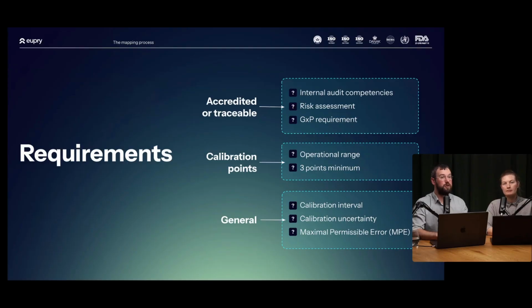You need to have a risk assessment as well. So if you choose to go for a traceable calibration, you need to have a risk assessment in place on how you ensure that the results are compliant. And then lastly, GxP requirements. There are some areas of GxP that do require that you choose a traceable calibration in some specific parts of it. So what would be an element of the risk assessment to make? First of all, I would say the major part of your risk assessment, as we've seen it, is: do you actually have the competencies to assess the technical expertise?